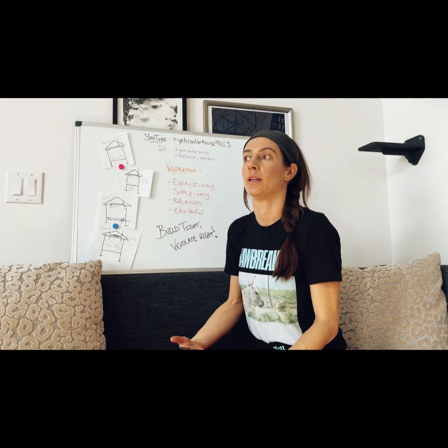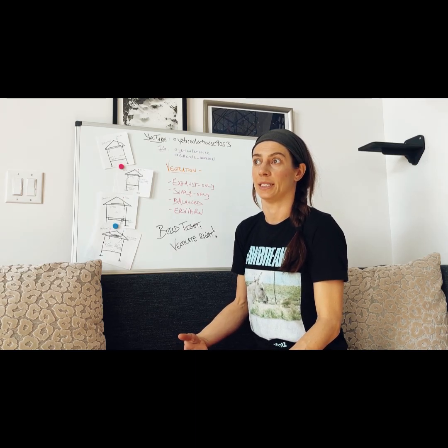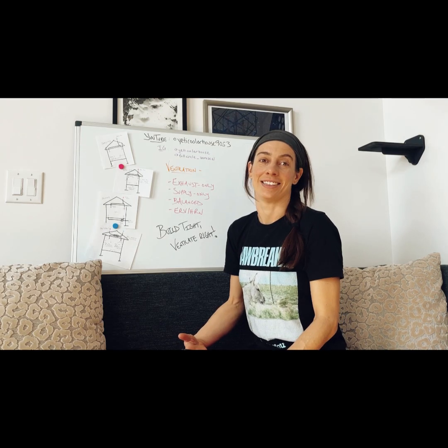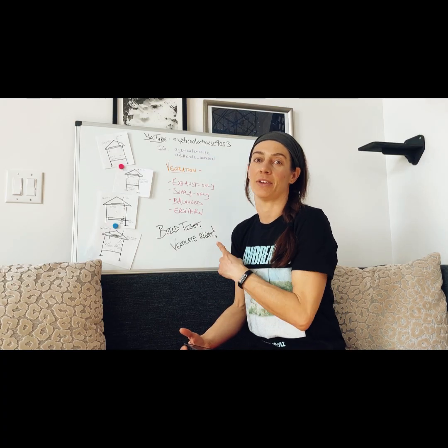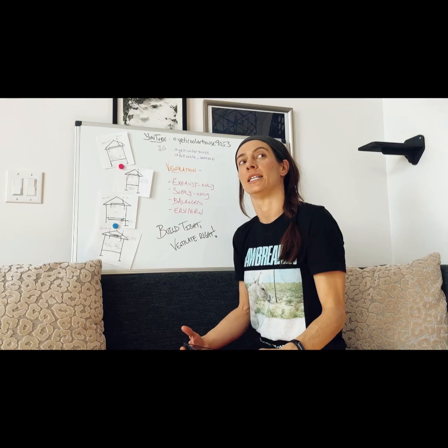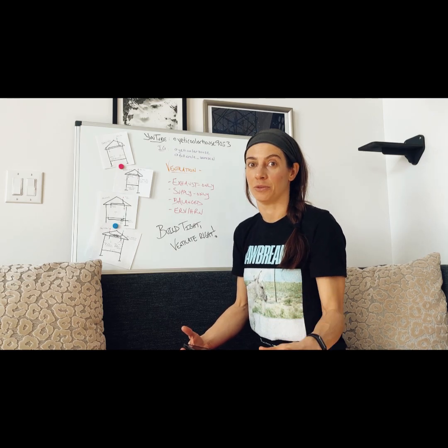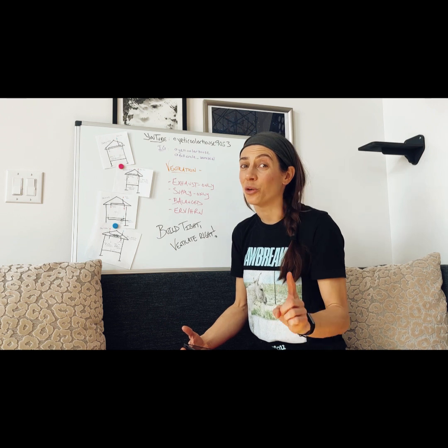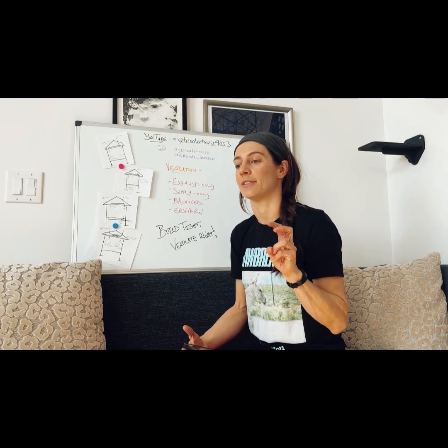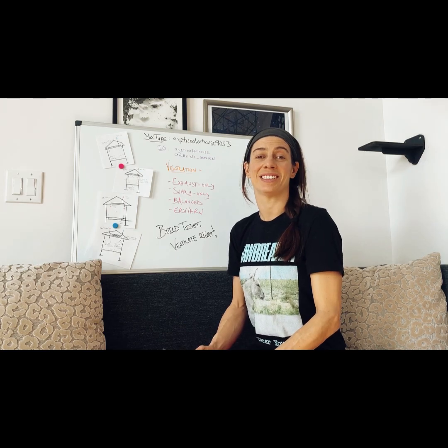Okay, so I am in Colorado, climate zone typically 5, 6, occasionally 7. Anyways, in this area, the most common type of ventilation we see is exhaust only. Essentially, that is your bathroom fans that are running continuously at a super low rate. I'll show you that rate at the end here. But that's the most cost-effective, easiest way to achieve the requirements. We built the tight house.